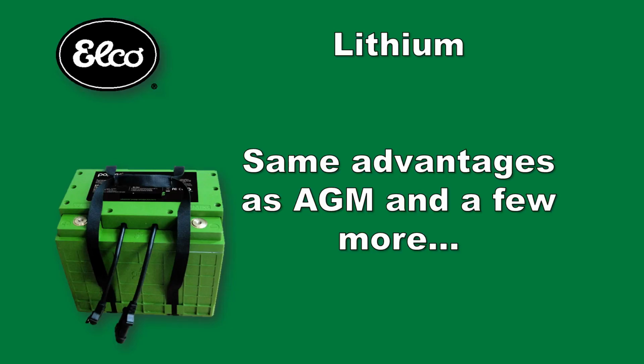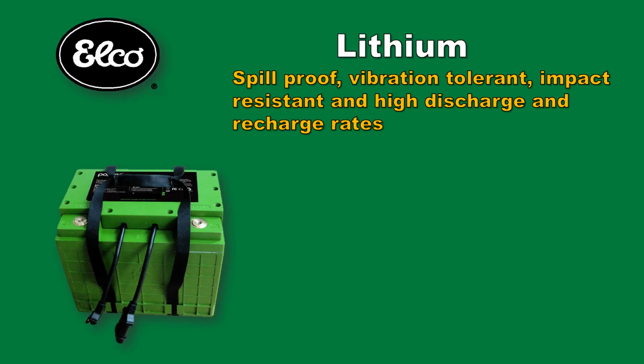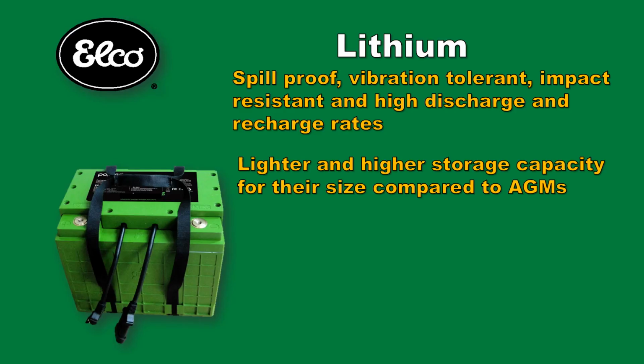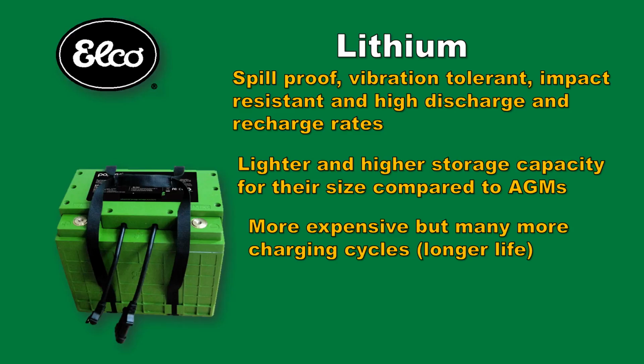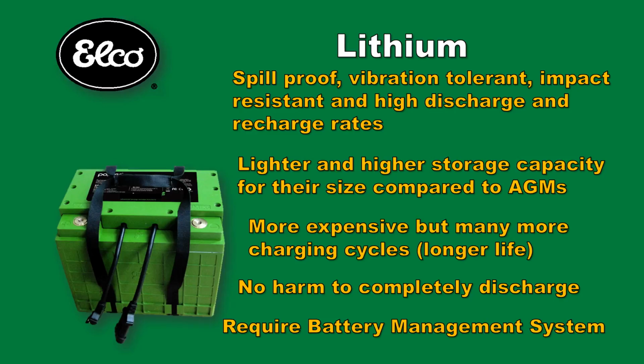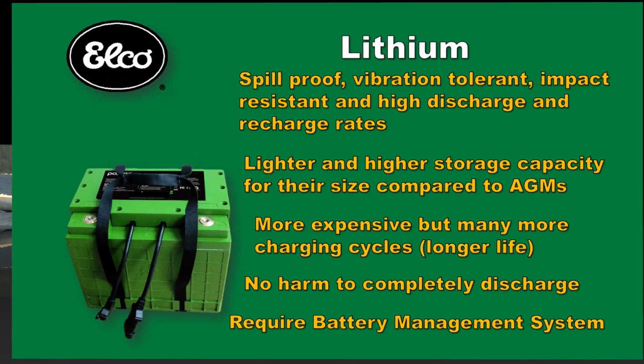Lithium batteries come in a variety of chemical compositions, with lithium as the primary active chemistry. Like AGMs, lithiums are spill-proof, vibration tolerant, and impact resistant to damage, and have high discharge and recharge rates. They are lighter than their AGM counterpart and have a higher usable storage capacity for their size. As mentioned, they are more expensive, but lithium batteries have many more use cycles than AGMs and are immune to damage from over-discharging. They require a BMS, which monitors each battery and analyzes information to control charging, discharging, and safety protections.